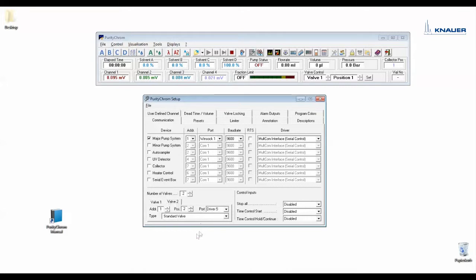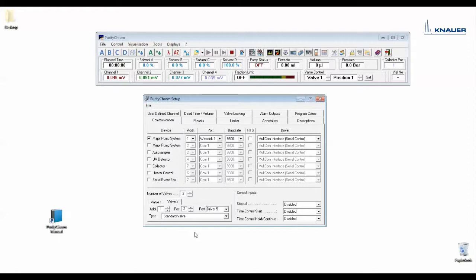The second valve is the valve of the fraction collector. You have to enter the valve of the fraction collector here too because the software discriminates between the collector and the valve that is normally in the arm of the fraction collector. The type is a standard valve, it has two positions, waste and fractions, and the port number is driver 5.